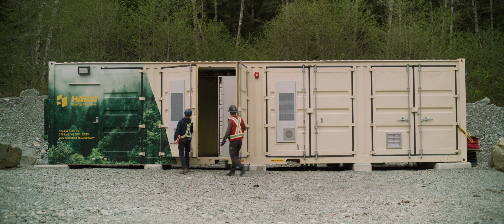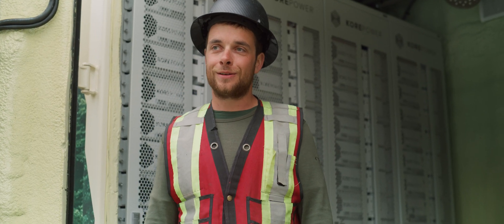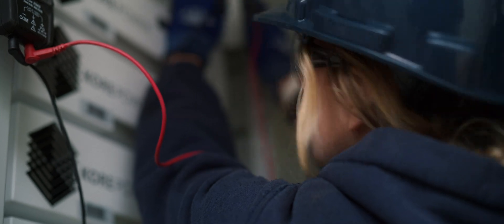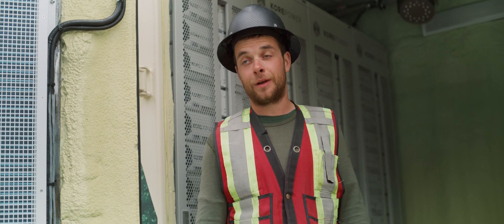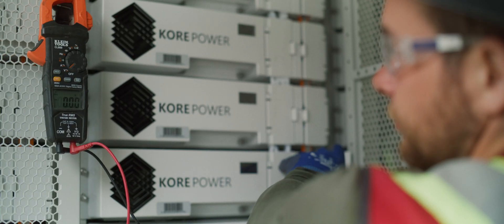This is the battery section of the system and there is 1.6 megawatt hours of storage here. It helps to absorb the energy from the PV when there's more power being produced than is needed. It also allows the generator to charge the batteries at a more efficient rate, so the generator won't be running all the time and it can be quieter at nighttime or during critical times.